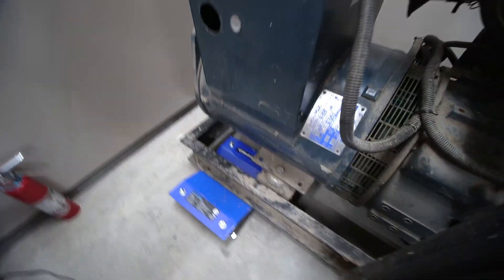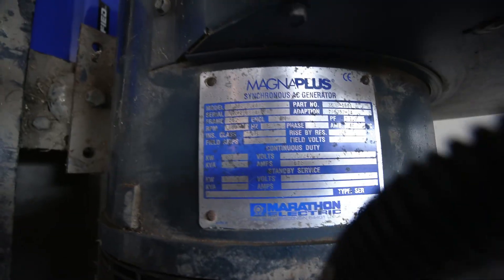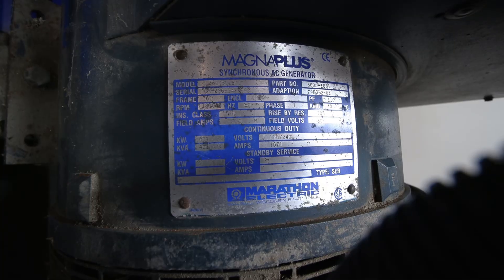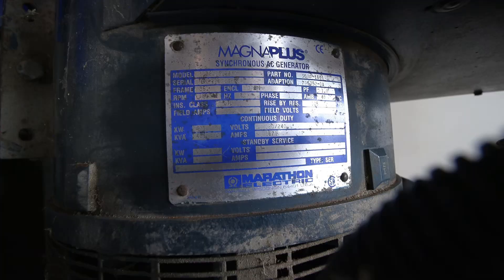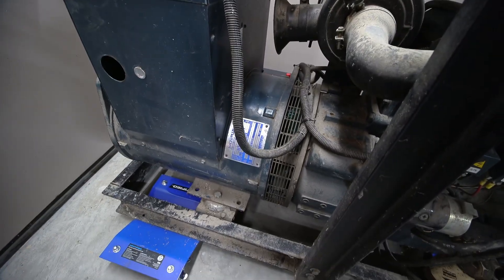Here's a closer look at the generator — pardon the movement, this camera is pretty heavy. I'll move around here so you can read the tag. The generator says it's continuous duty — standby duty isn't even stamped on it. It's a 401-kilowatt generator on the back of this thing, and yes, it's pretty big. It may be a little bit deceiving in the actual video, but it is a pretty big generator.